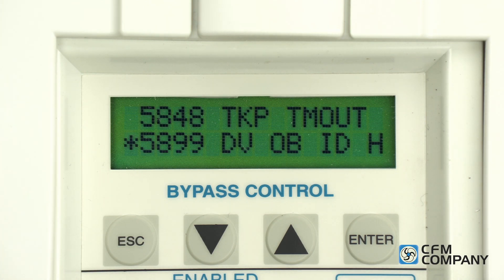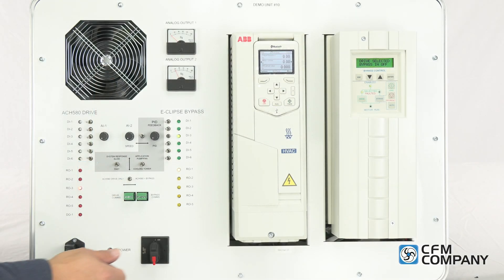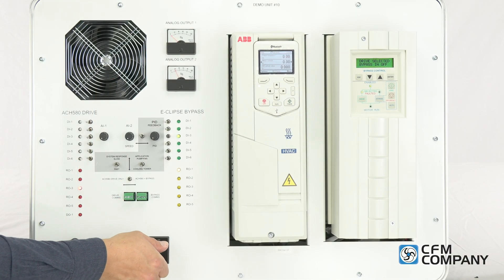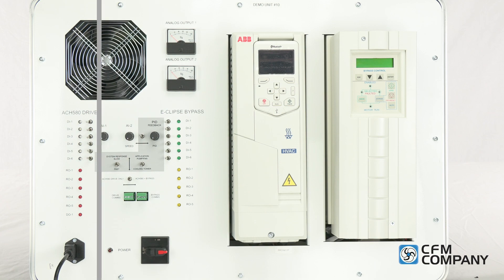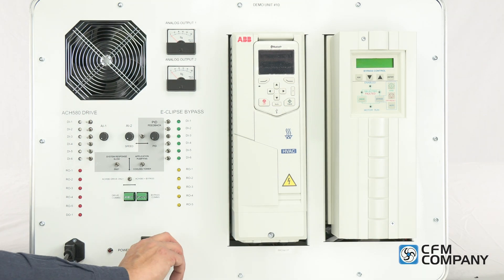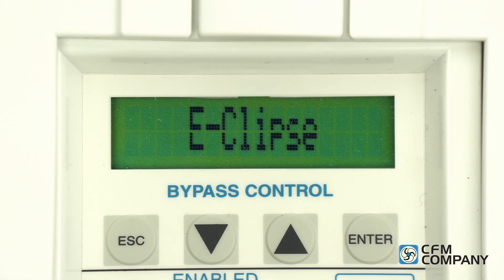Once the BACnet parameters are programmed, the drive must be power cycled. Simply turn off the power to the drive enclosure using the main disconnect. Allow both the Eclipse control panel and the drive control panel to go black — this can take a few minutes. Once both displays are blank, apply power to the drive. The new BACnet settings will now be active.